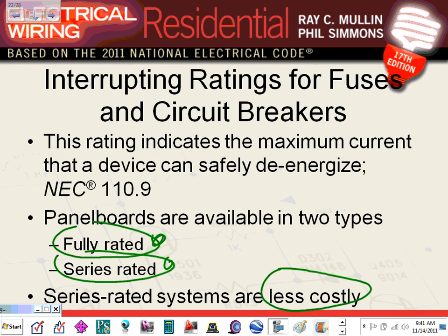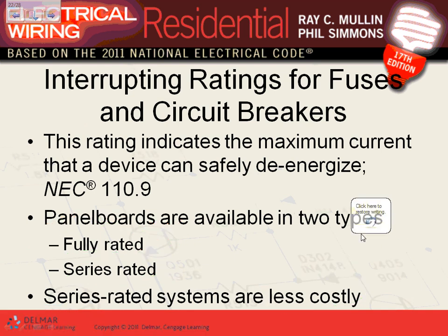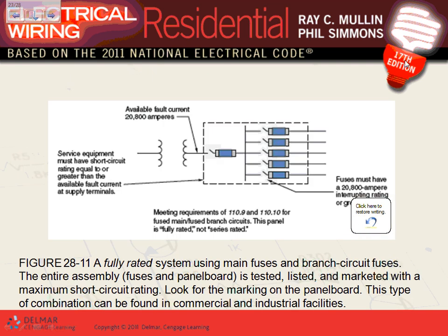We will talk about them in detail, guys, when we invite the Square D rep. When he comes here, he shows you a lot of equipment. So that's the only reason. Otherwise, everything will be fully rated. So what's the default? The default should be right here. This is your default. The default is fully rated equipment. Series rated equipment is the exception. So what the heck do they mean? Let's go directly into a panel. Here's a fuse panel, guys.